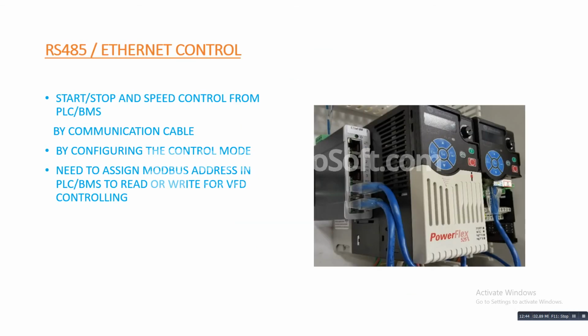The last one is communication mode, by RS485 or Ethernet port. Using this communication mode you can start and stop the VFD from a PLC or BMS, building management system. From the BMS or PLC you can connect directly with a serial cable or Ethernet cable to the VFD, and you can control this VFD. You can control it and monitor it also.